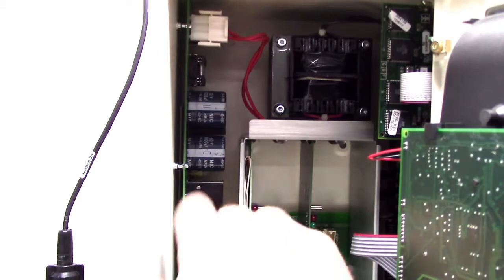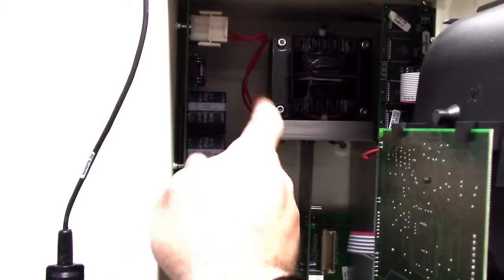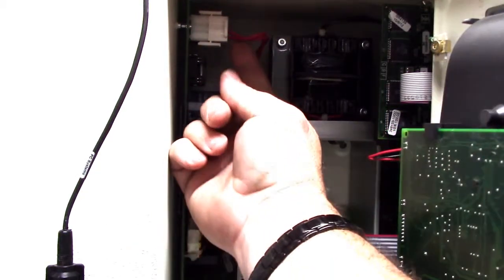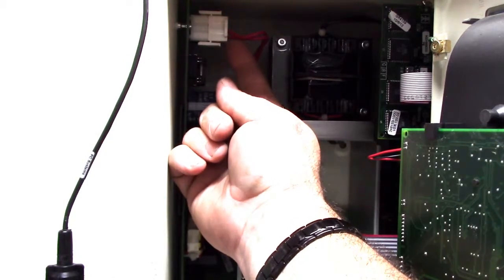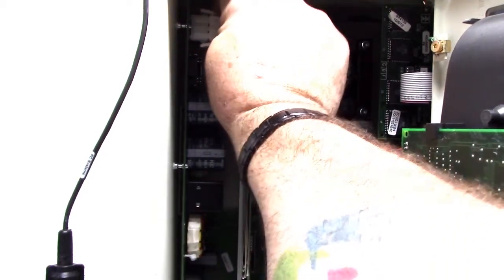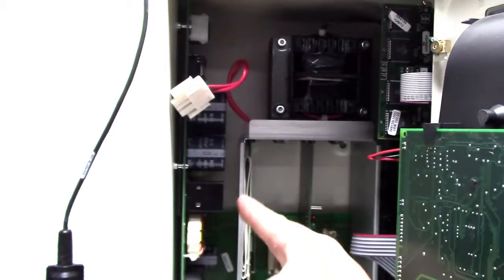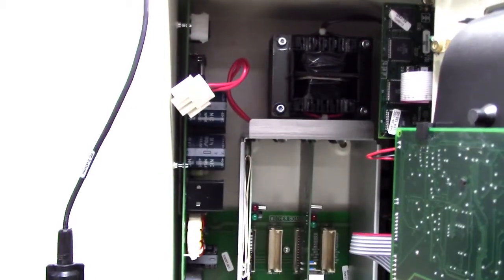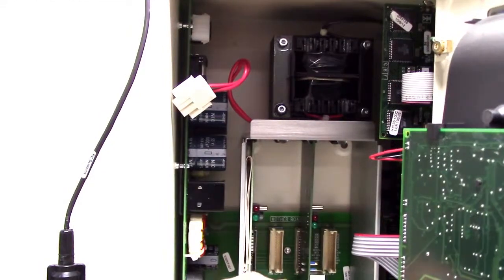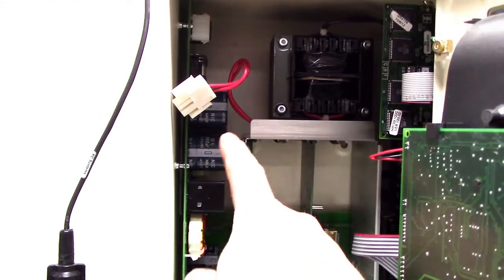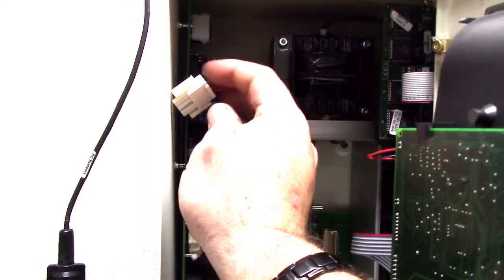Remember, power is still on to the tank monitor. We're going to take this white Molex plug with the red or pink wires, depending on the age of your tank monitor, and disconnect it off of the left-hand power board right here. With the battery switch still off, let this Molex plug unplug for about 10 seconds.